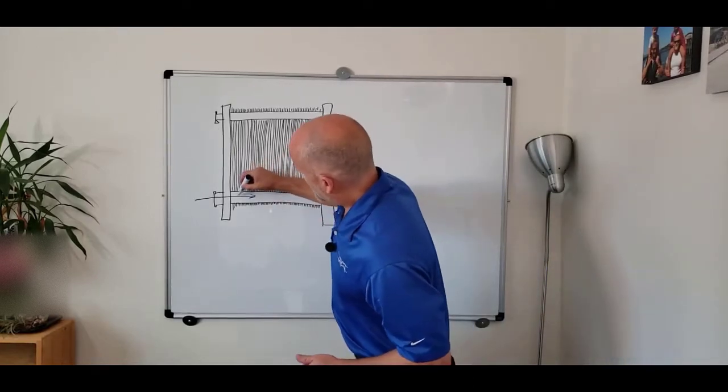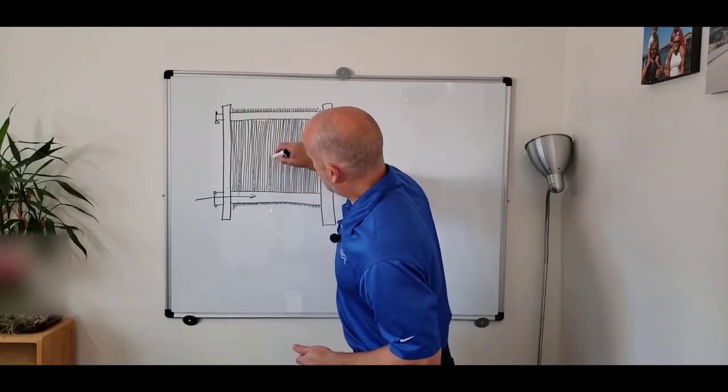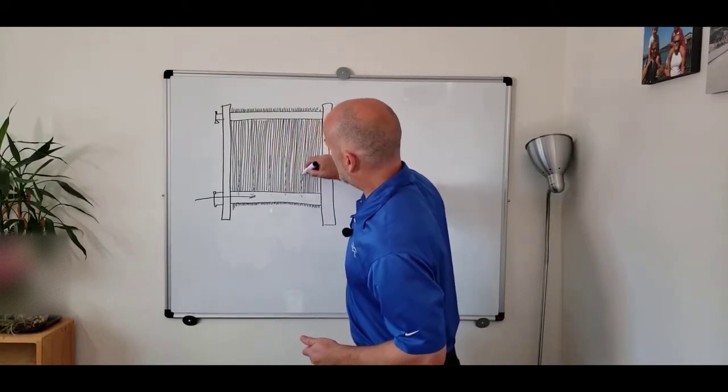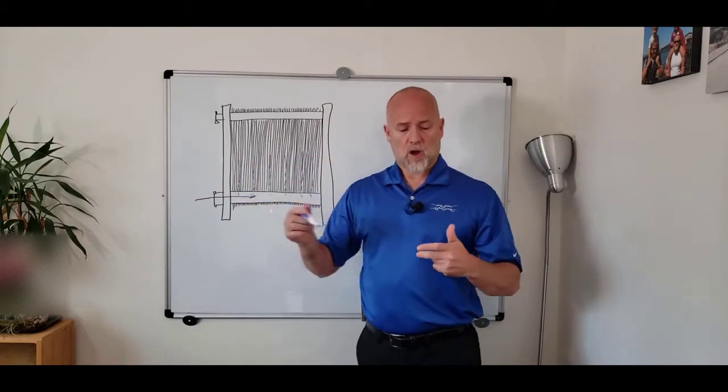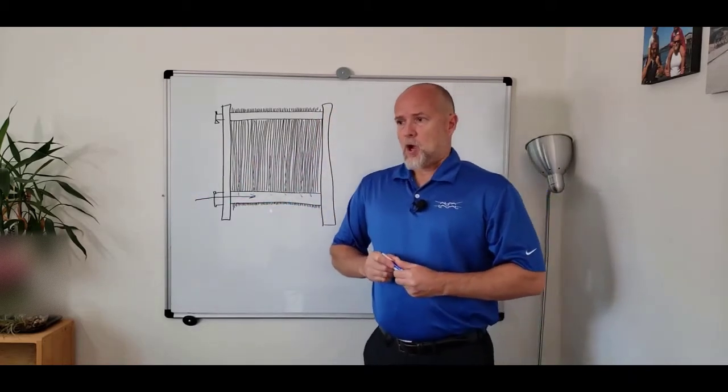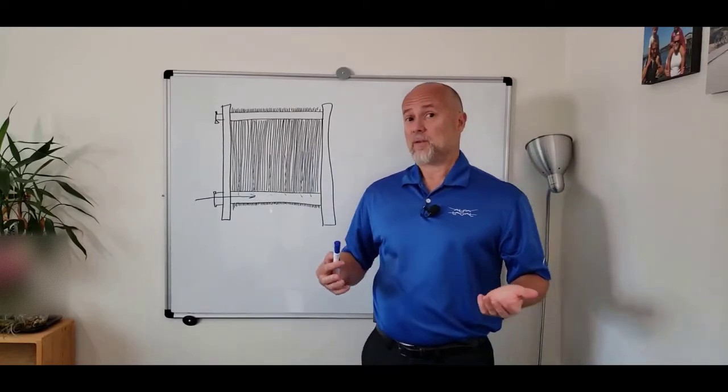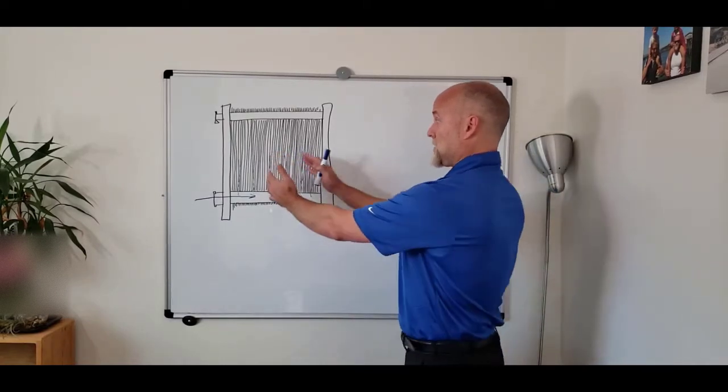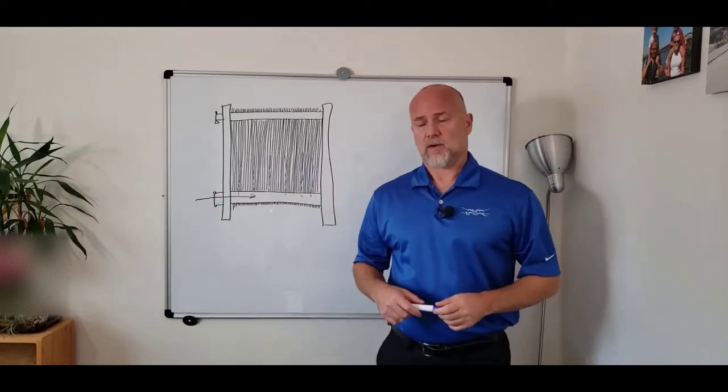So you have this cold flow going up and you want to design your plate pack in a way that you cover the whole length. Considering that in larger exchangers you have up to 800 plates, you can see how this plate pack can be very wide and the distribution needs to be taken into account.